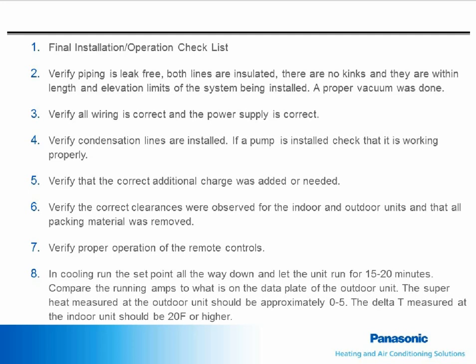The air temperature drop, known as delta T, through the indoor coil should be at least 20 degrees. If the humidity in the room is low, the delta T could be as high as 35 degrees. Remember to complete a good installation and minimize callbacks. The end user should be shown how to use the remote and operate the unit.